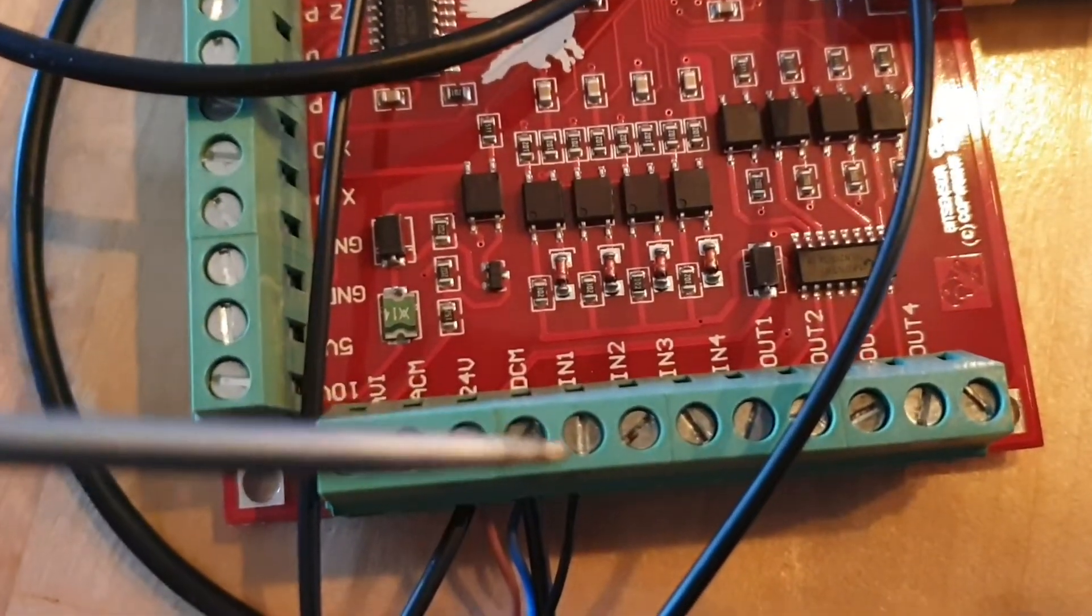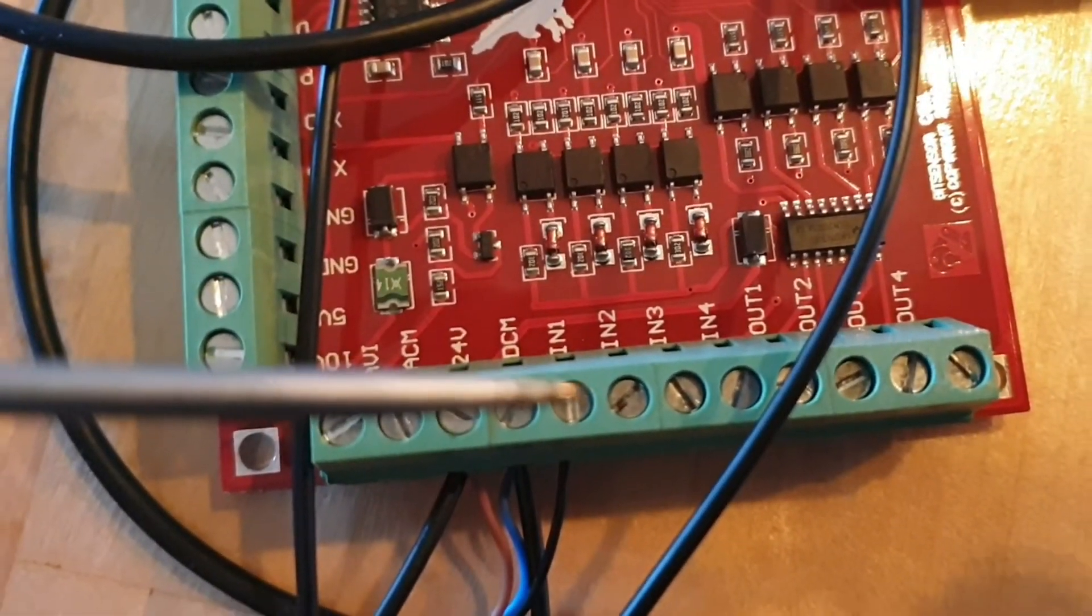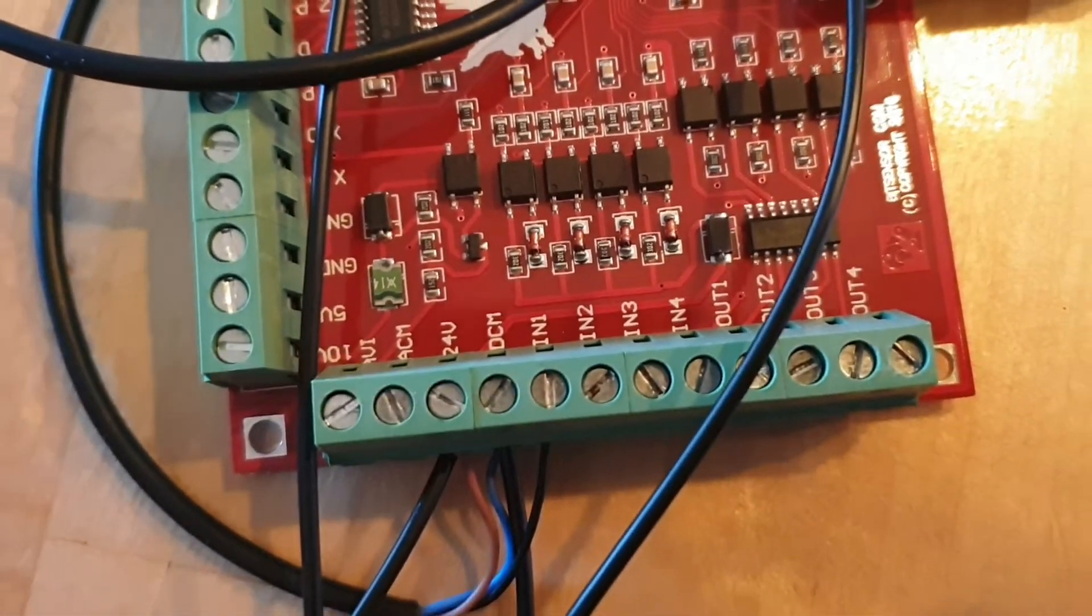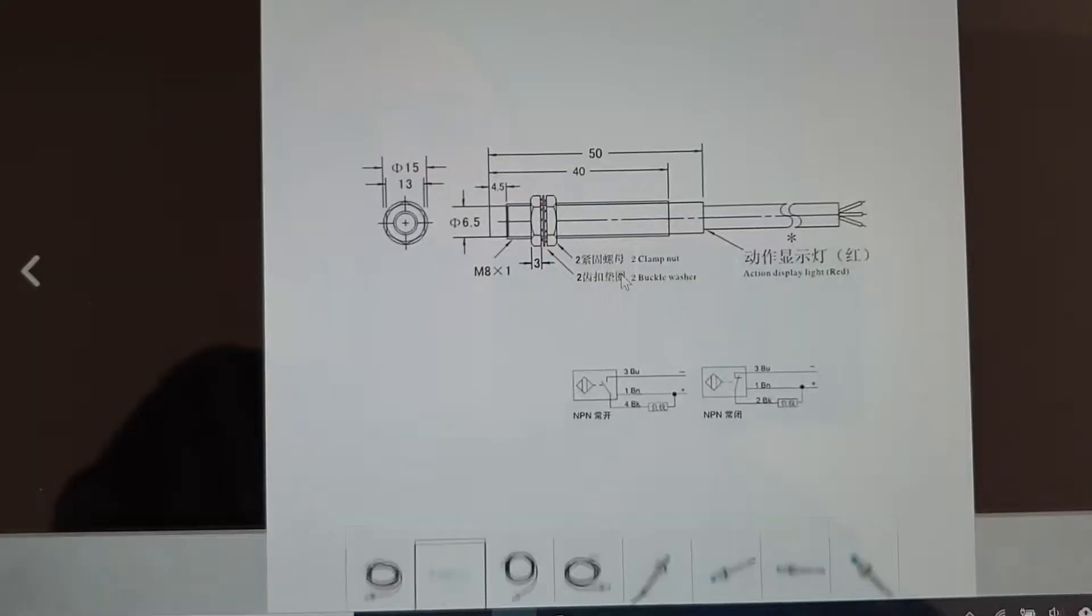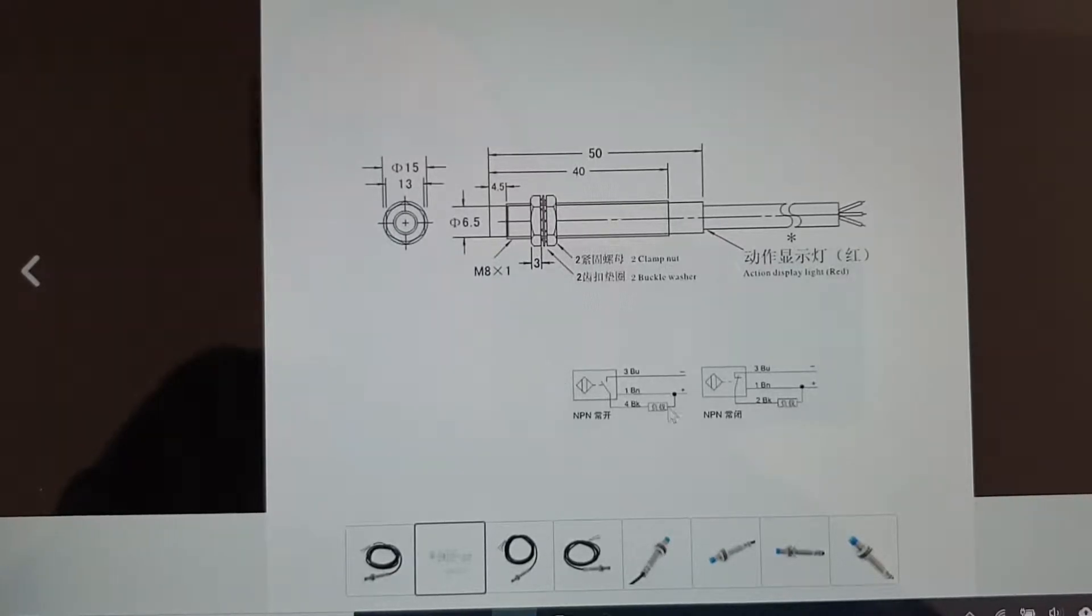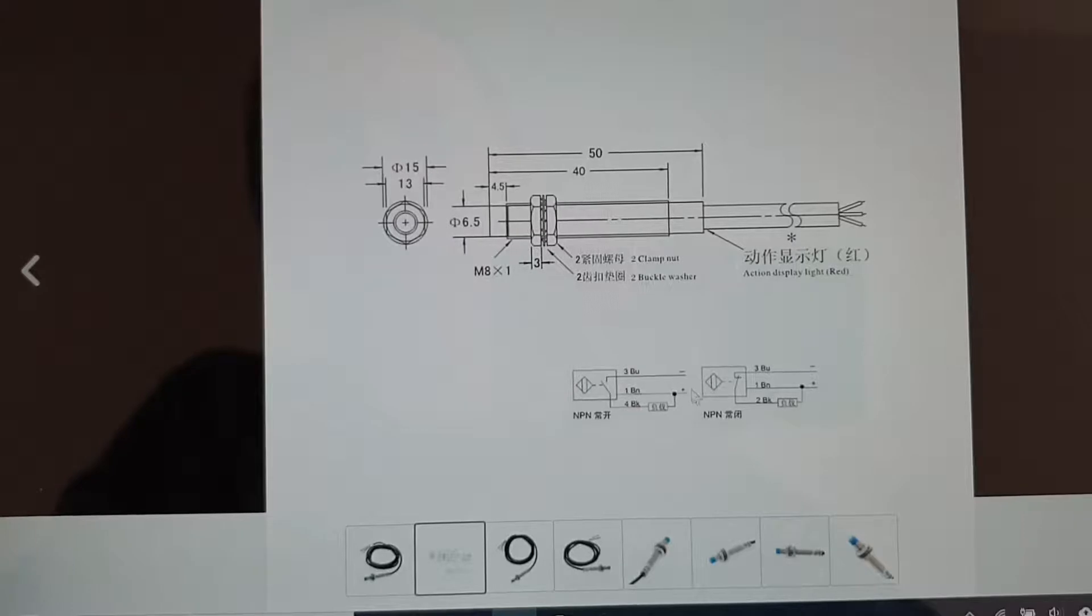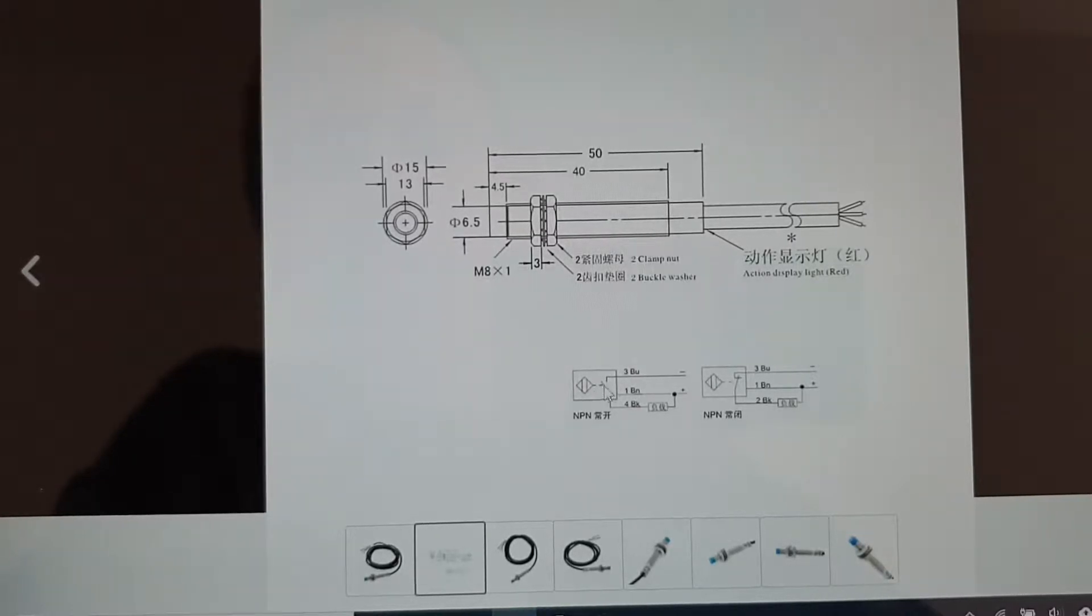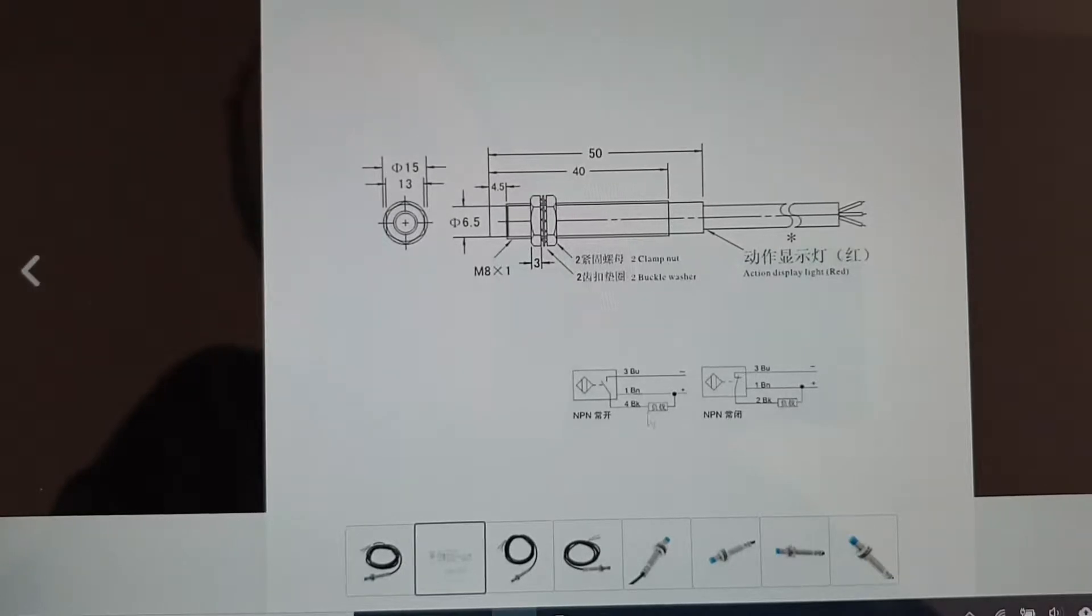The output of the limit switch is connected to IN1. A quick look at the wiring diagram for this sensor shows that the load should be connected to the black wire and positive. When the sensor is active, the negative side of the load will be activated.